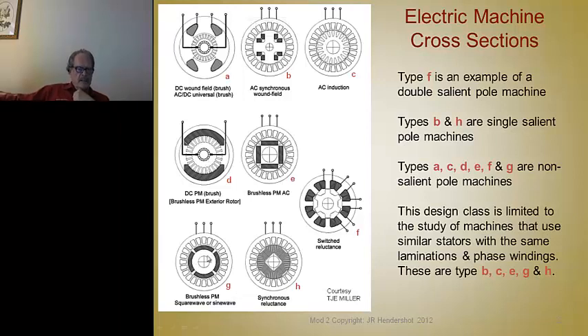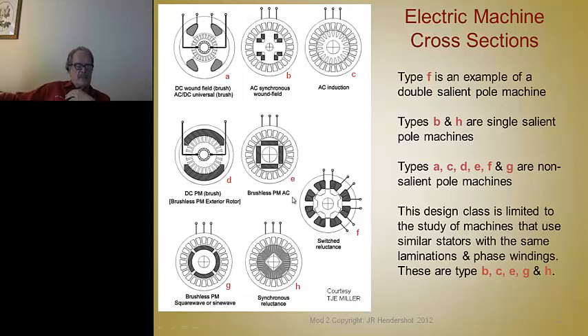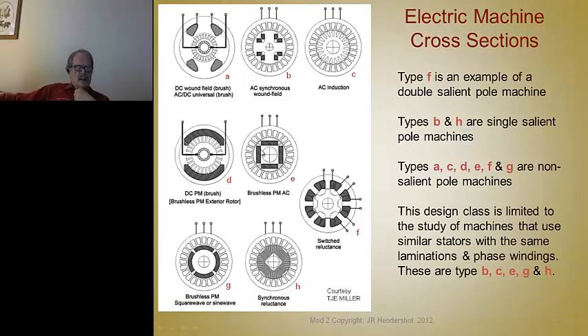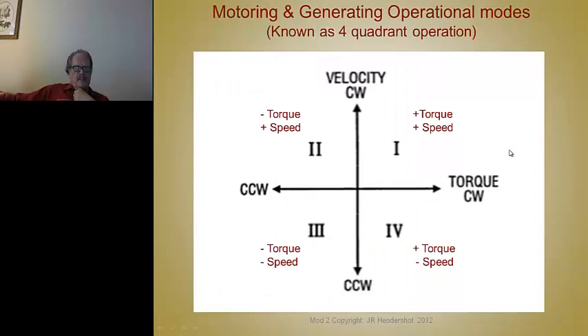Taking this motor with magnets on the surface — called an SPM, surface-mounted magnets — if you take the rotor core and put slots inside it and stick the magnets on the inside, that's now known as a brushless permanent magnet AC machine, or permanent magnet synchronous machine. You get torque from the magnets, but there are also soft iron poles between the magnet poles, and you can adjust those to vary the reluctance torque component.